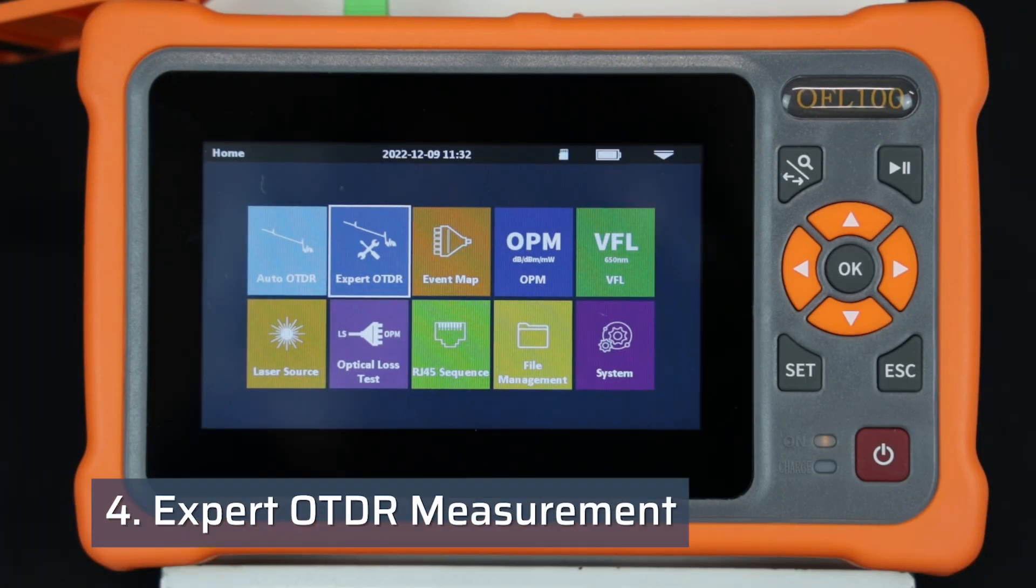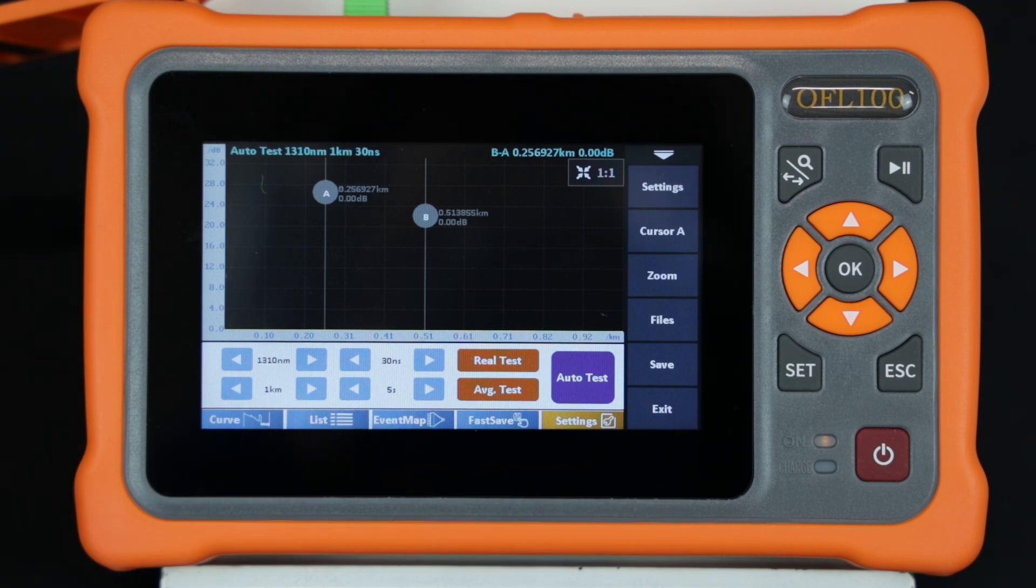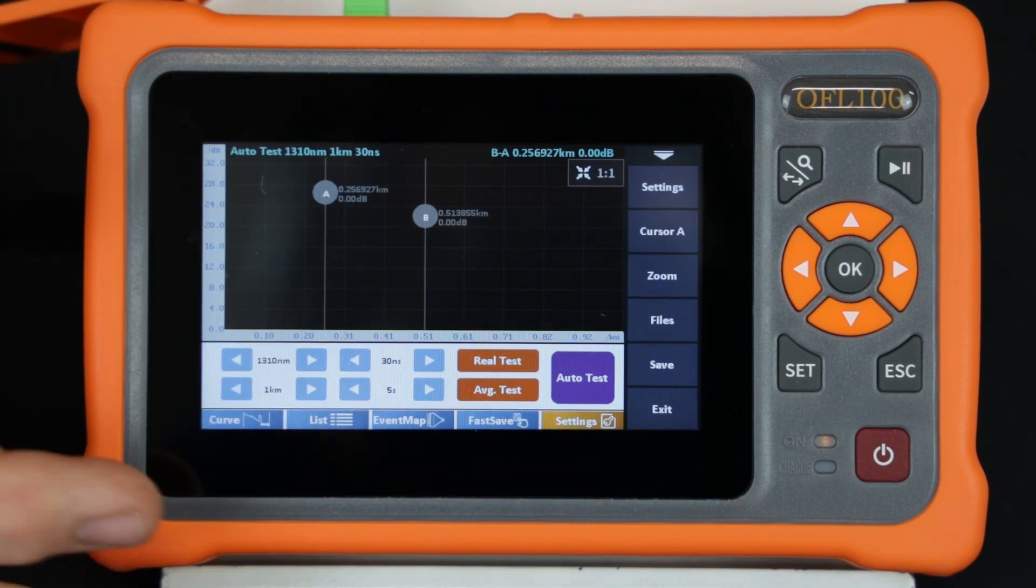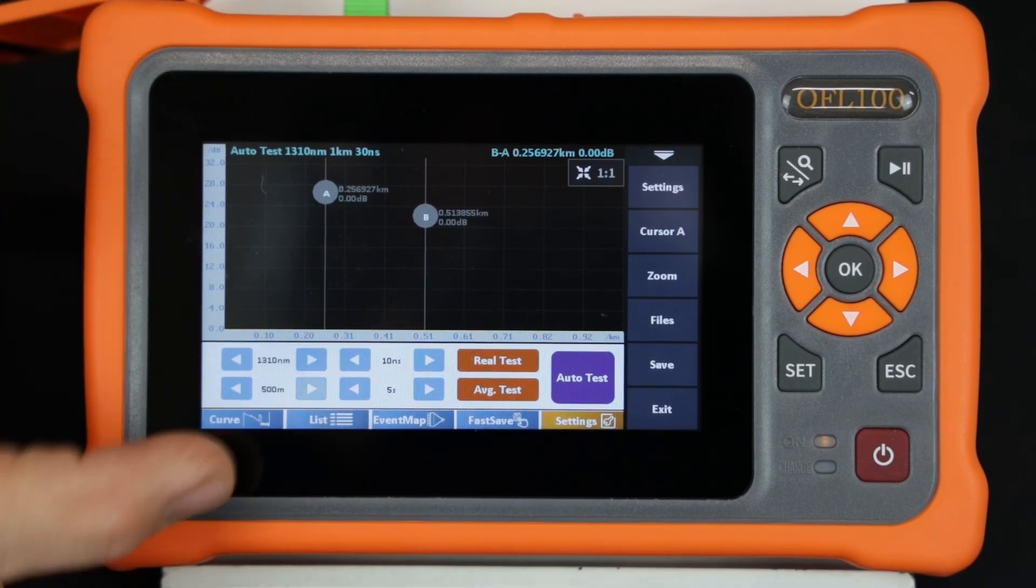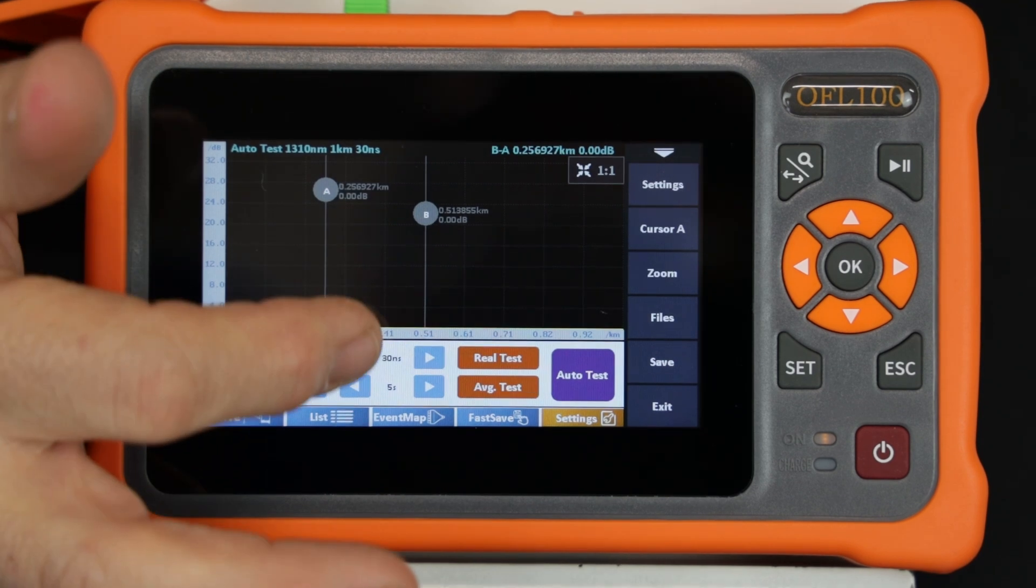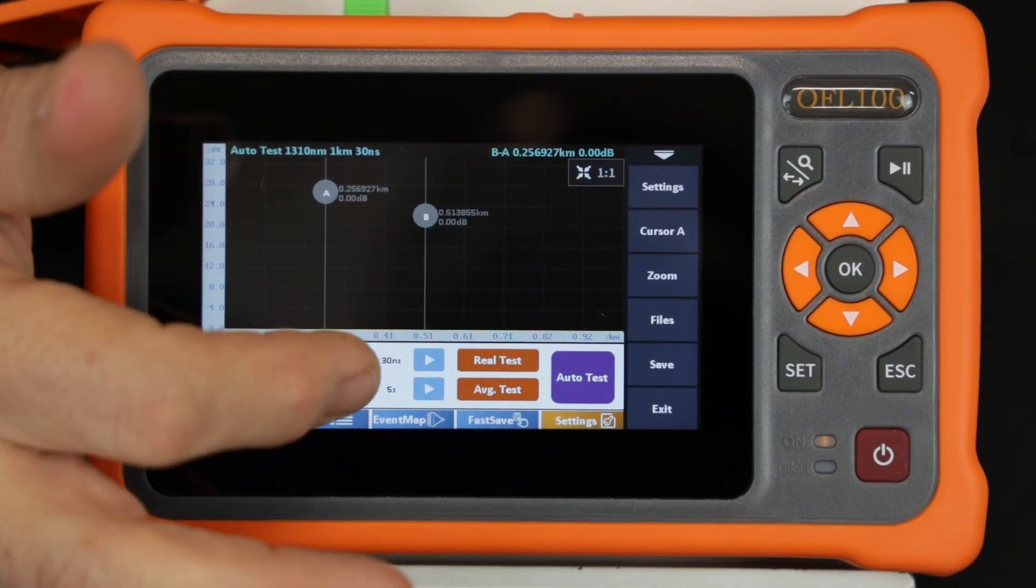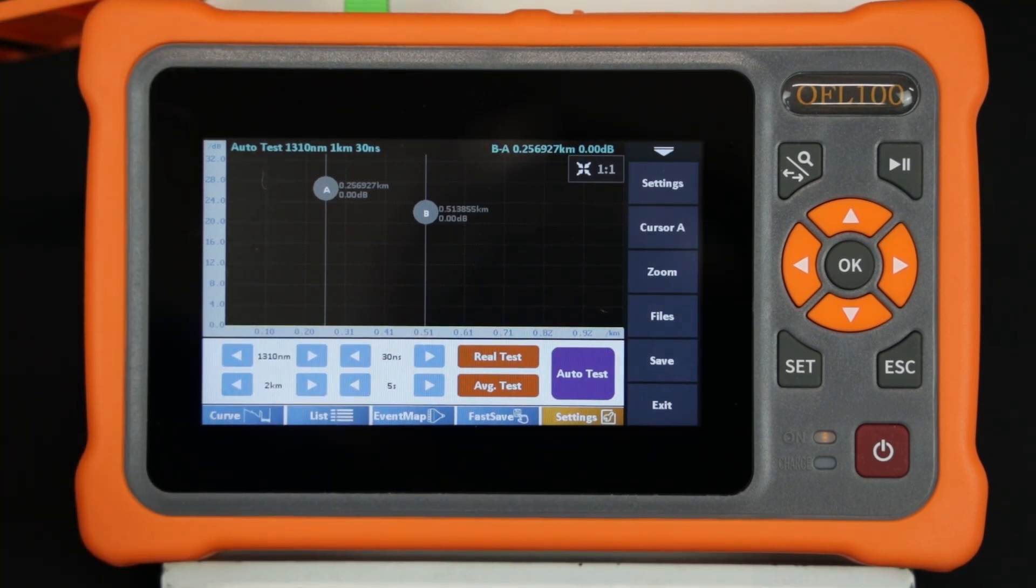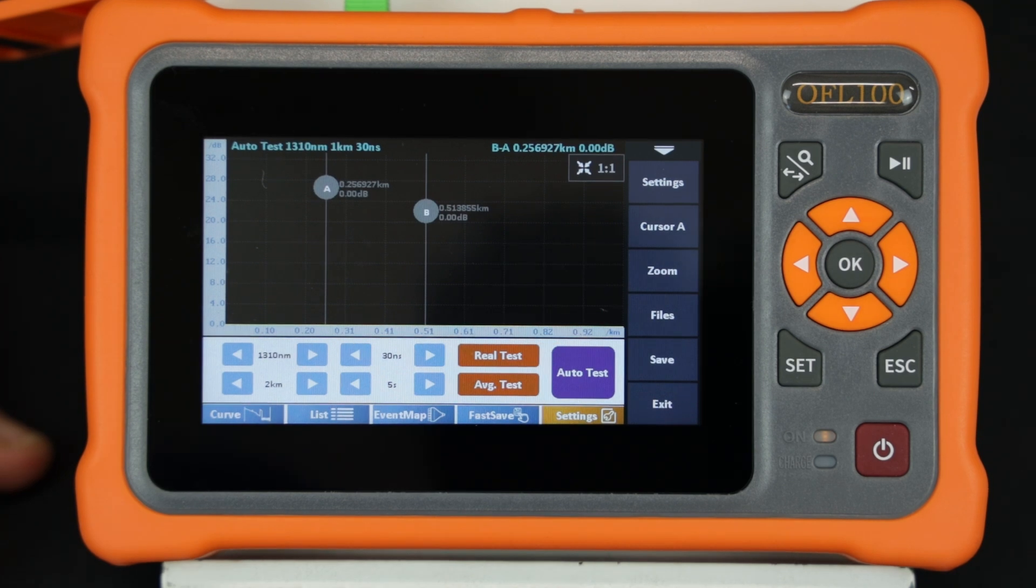Select Expert OTDR mode from the main menu. The Expert OTDR test settings provides the technician the opportunity to set all test parameters as desired. The wavelength, range, pulse width, averaging time, refractive index, and unit of measure can all be accessed and set to best suit the measurement to be undertaken.